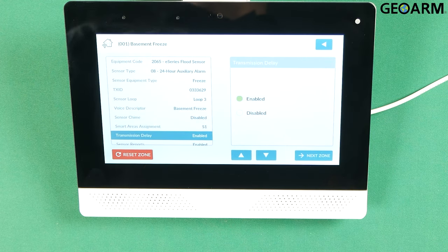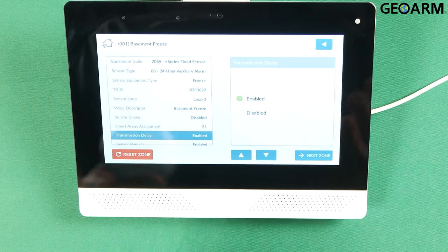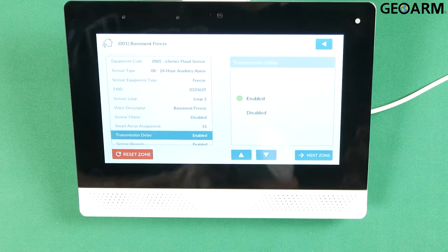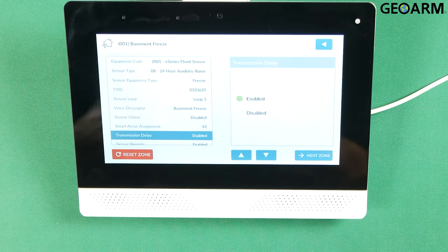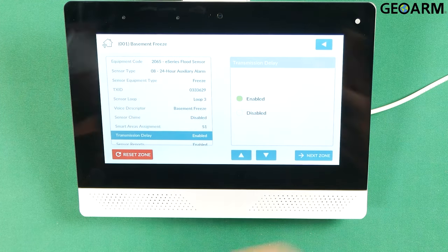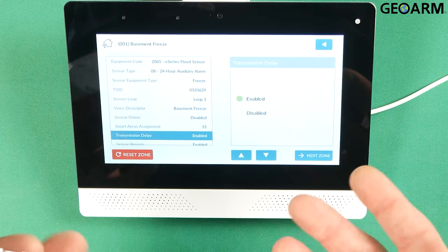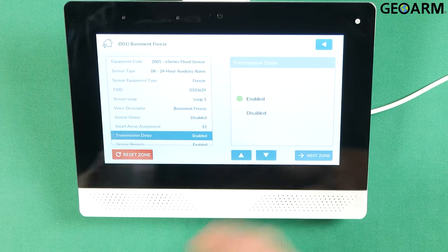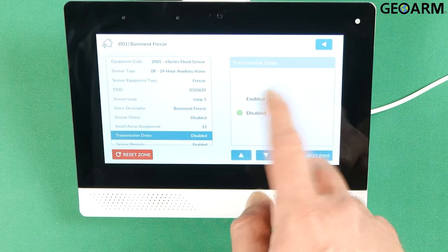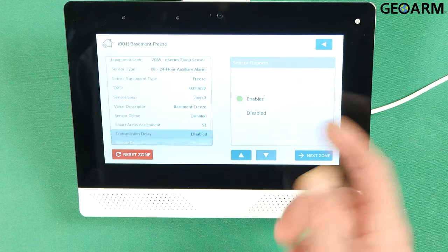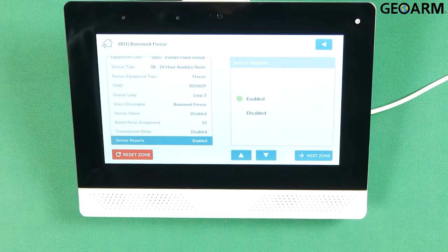Transmission delay. Now I don't like transmission delays because it adds another delay on top of whatever delay is already programmed in there. So I always disable that. I'll choose disable and then press the down arrow.